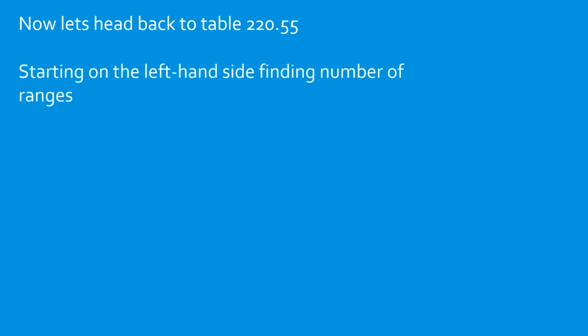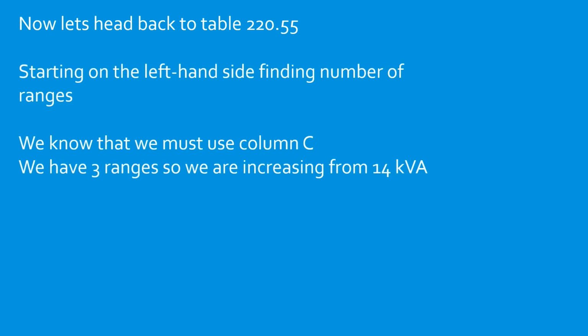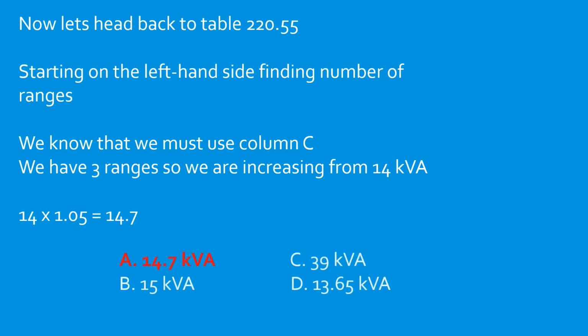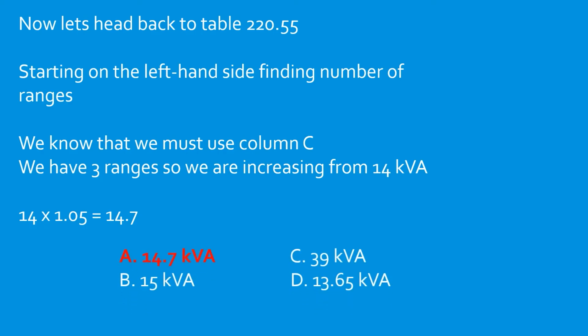So we go back and we use our table like normal. So we start on the left-hand side. How many appliances do we have? We have 3. So we come over and we find the value for 3 appliances. And in this case, it's 14. So we find it, and we know that we have to increase that value by 5%. So we take 14 multiplied by 1.05, and that's going to give us our increase of 0.7. So we're going to select 14.7 kVA.